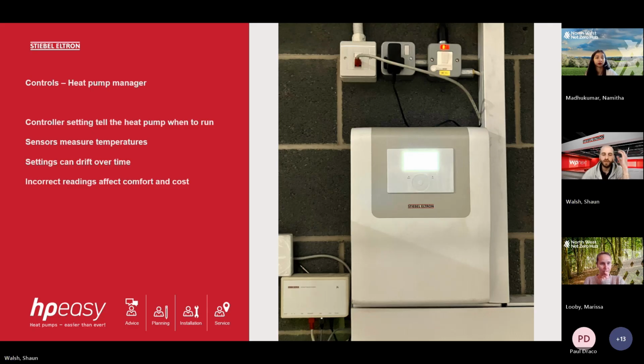And what can happen with sensors over time is they might get pulled out of pockets, or cables can be damaged. As a real world example, if the cylinder is in someone's garage with the sensor in the pocket, and then they go in and start moving boxes around, they may pull a sensor out or dislodge it from where it's supposed to be. Then the heat pump can't react as it's meant to because the sensors aren't positioned where they need to be.